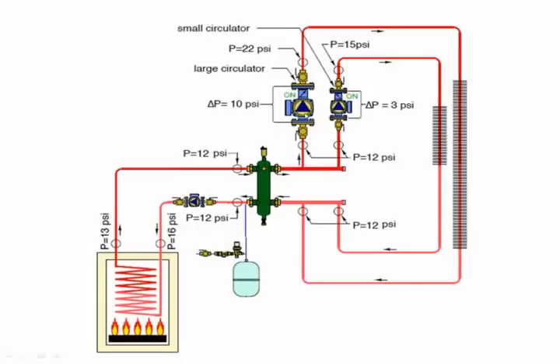Now, if our second pump turns on, it turns on without impacting the flow rate on our first pump. So they're completely decoupled from one another. Now, with the appropriately sized hydraulic separator, we could put a whole bunch of pumps over here, okay? And they'll all be decoupled as long as we follow those rules.